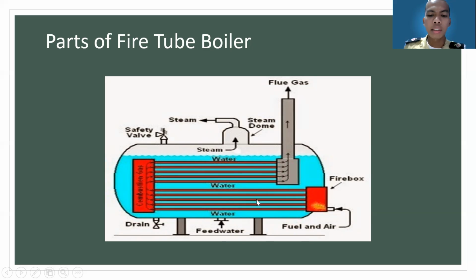And also the pressure gauge. The pressure gauge is situated on the top of the shell. It shows the amount of pressure inside the boiler. It indicates the pressure in various units like psi, and presently digital instruments are used which sense the pressure by a transducer, and a signal is sent to the display unit.